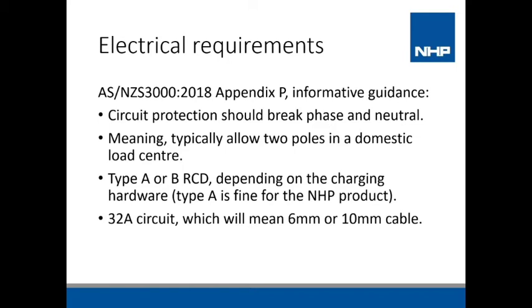Circuit protection should break phase and neutral. So this typically means allow 2 poles in a domestic load center or allow a long body that'll do the neutral as well. You need type A or type B RCD depending on the charging hardware. So what this is getting at is because the EV has a big rectifier in it, it is effectively a really large switch mode power supply. The concern that the regulators have got around that is that this can create DC leakage currents. In the presence of DC fault currents, we can end up with a type A RCD not working correctly. The DC fault current can swamp out the function of the RCD.